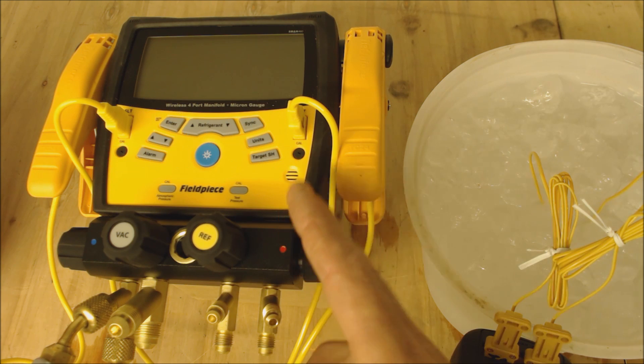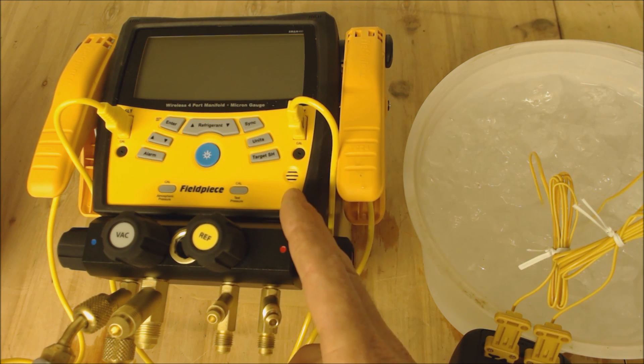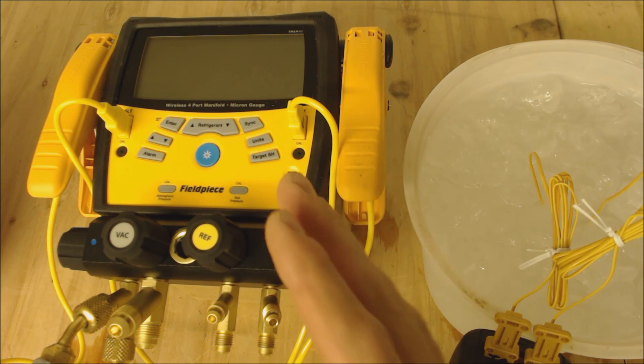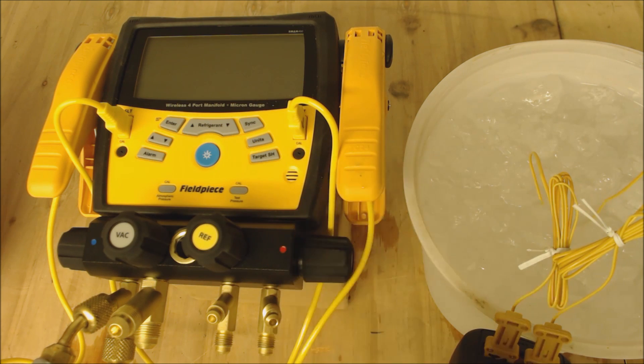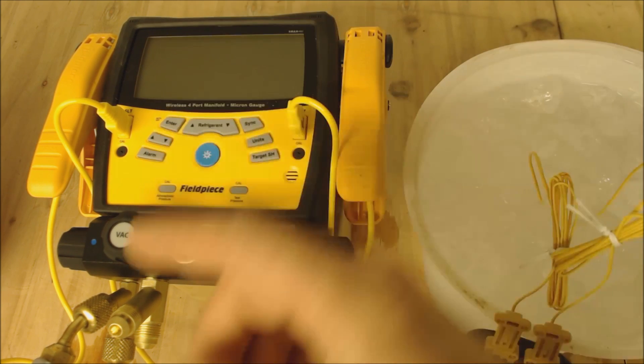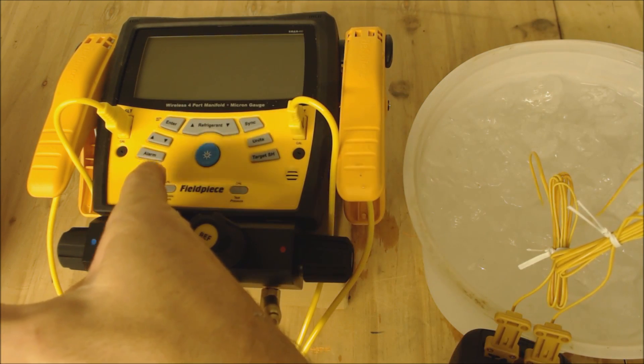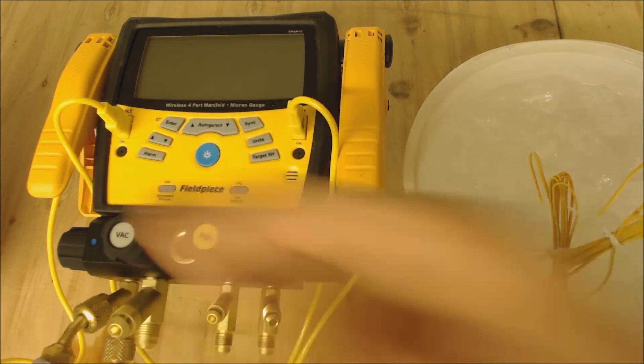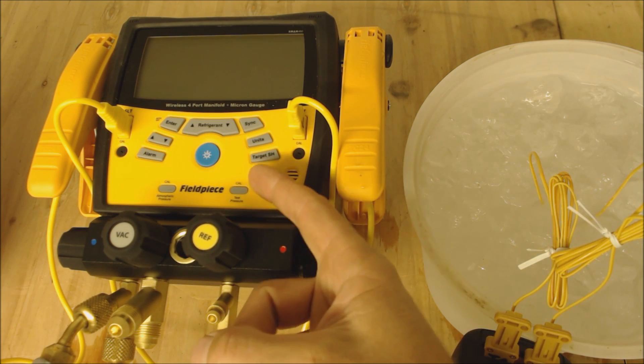Hey guys, this is AC Service Tech. Today we're going over the calibration of a digital manifold gauge set, specifically the Fieldpiece SMAN 460. You're going to have to calibrate the temperature sensors, the zero atmospheric pressure, and the test pressure.